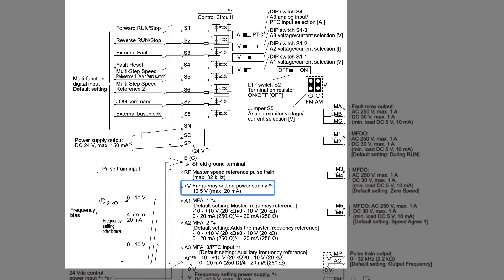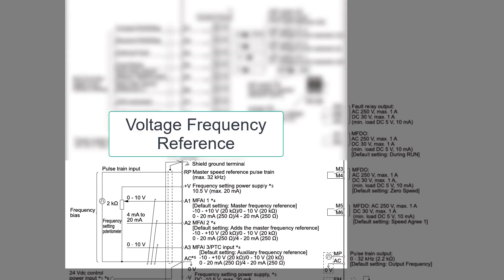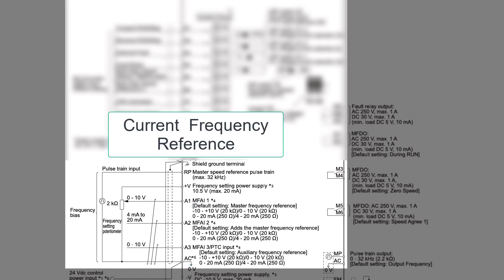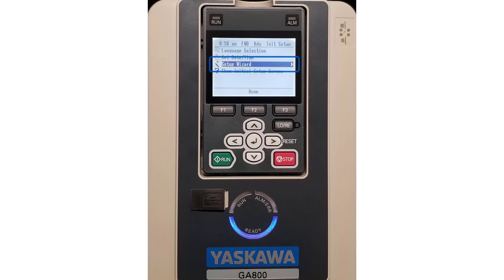Terminal +V is a 10-volt and 20-milliamp source for devices such as potentiometers and pressure transducers. AC is the analog input common. A1 is the first of three multifunction analog inputs and is the default setting for the master frequency reference. Connect a speed reference device that uses voltage to terminals AC and A1. If using a speed reference device that uses current, connect to AC and A2. In addition, if the product has the drive setup wizard, it will tell you what connections to make for several different configurations.